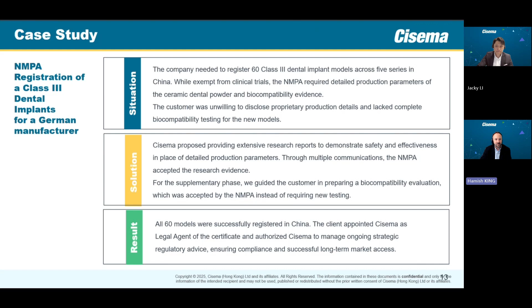Biocompatibility for dental, as with other products, can be a key concern, and NMPA often views biocompatibility requirements more strictly than other authorities and will require increased evidence as compared with other authorities. So, although biocompatibility reports are the one type of test report that can be accepted from overseas labs, provided they are GLP compliant, we encourage you to check your biocompatibility reports to see if they are sufficient to be accepted by NMPA and if they are wide enough to cover NMPA requirements. We were able to successfully support the customer in this case to obtain the approvals.